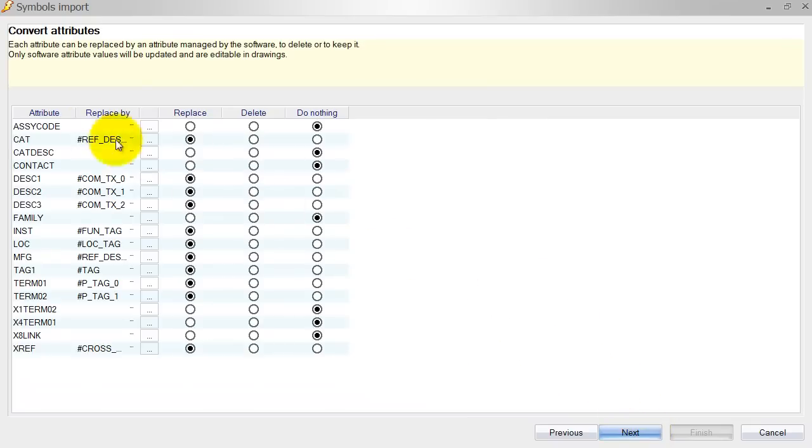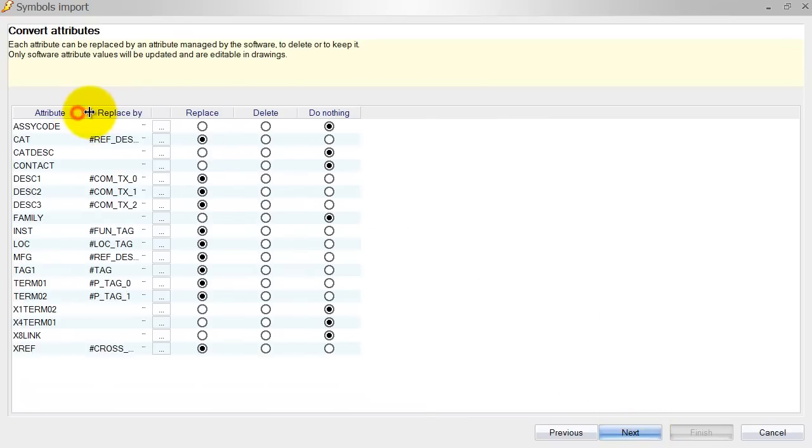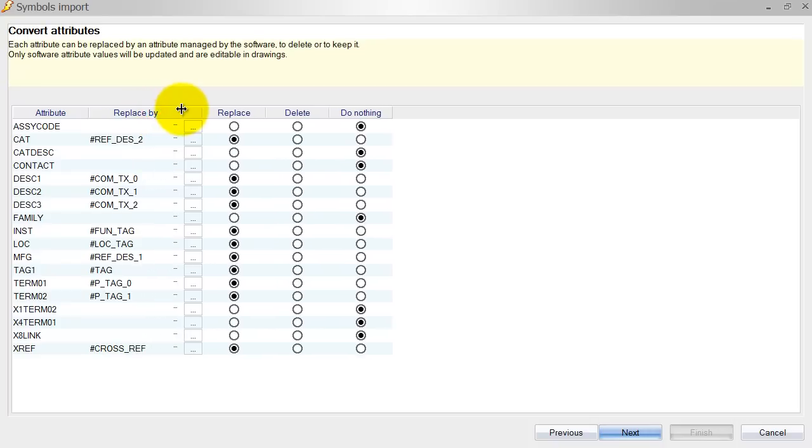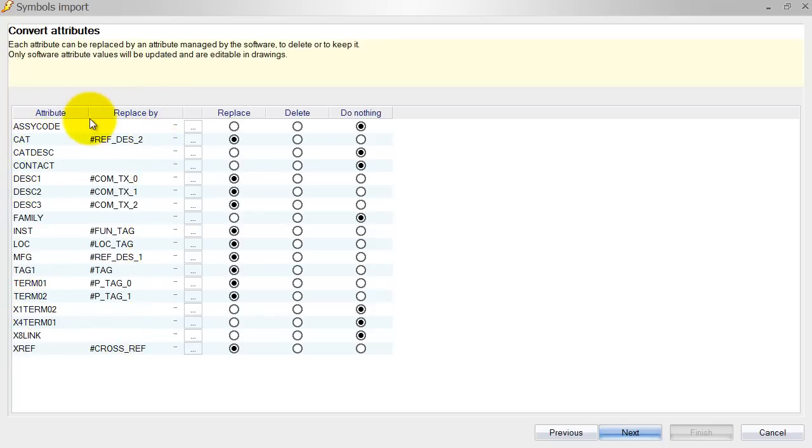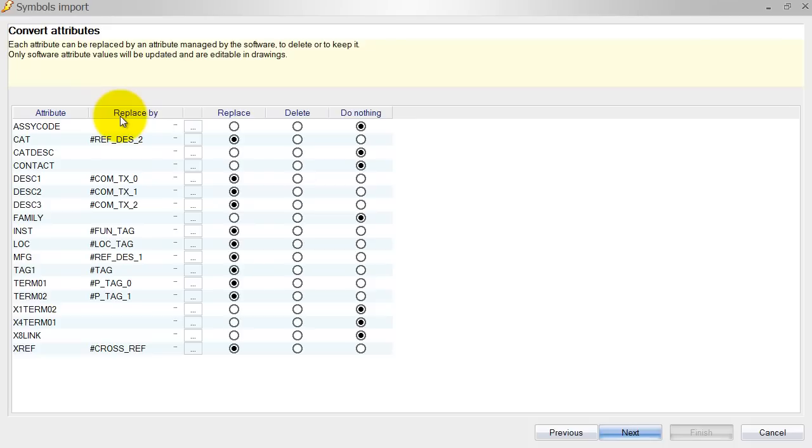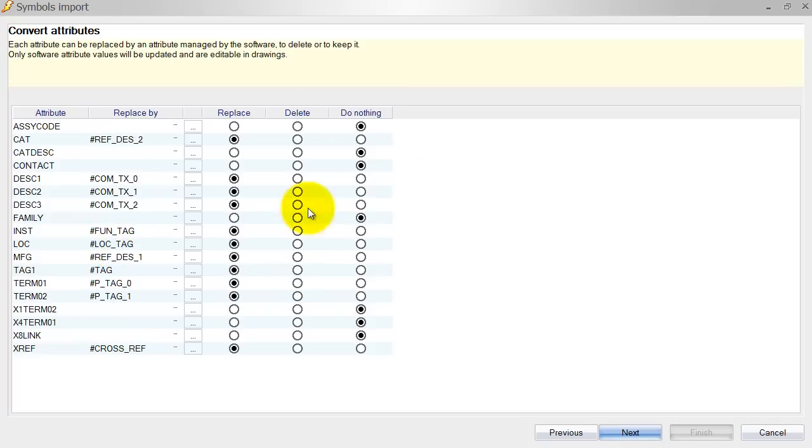Now this is what I mean and this is why you want to use an import configuration file because you can see the attributes used by AutoCAD Electrical and those are the attributes used by SOLIDWORKS Electrical. So if you import or export symbols out of your program that you've used before, you have to map them to the SOLIDWORKS Electrical attributes. It can do that automatically as you can see over here. I usually prefer to delete them and place them again myself. But let's just go ahead and do nothing for some of these symbols and replace for the other ones.